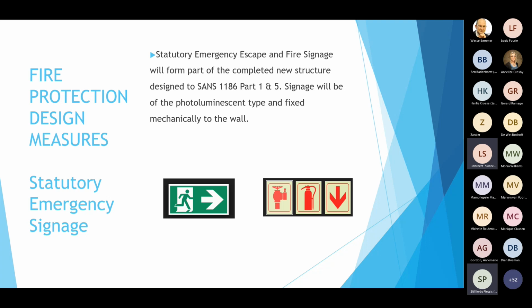It's a certain method of installation, and that refers to every fire-related sign needing to be fixed mechanically. So the usage of glue or double-sided tape is not acceptable, based on the reason that when the sign and glue get hot due to heat from wherever, your sign will fall off and you won't see anything inside the building to get out, nor will you have visibility going from outside to inside.